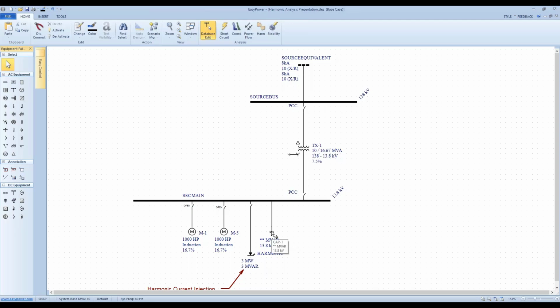It does have some meaning to put the capacitors online during the measurement, just to evaluate the impact of those capacitors and whether or not there's power quality issues being caused by those capacitors. But if the purpose of the harmonic measurements is to create a system model, the first thing you need to do is take these capacitors offline and then take your measurements.